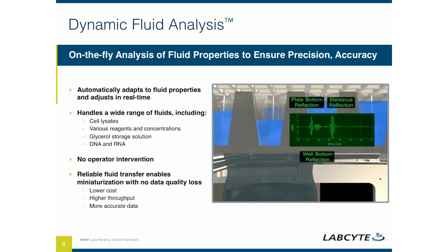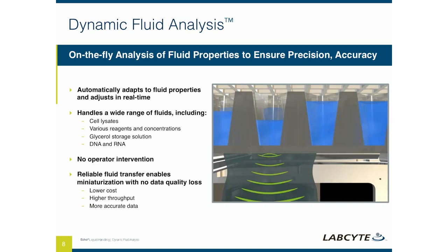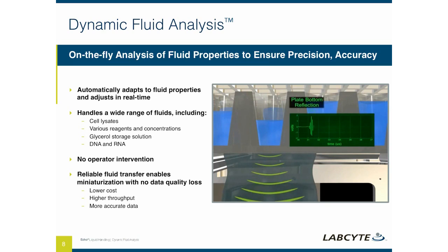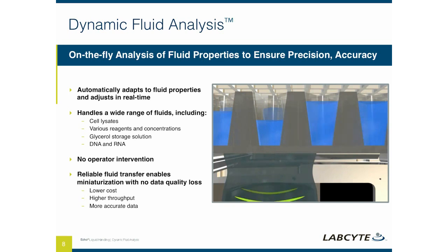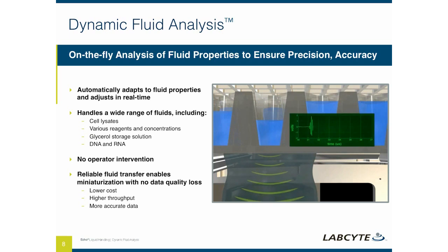So what you're looking at in this video is a situation where the transducer is emitting a low energy pulse into the well. We get reflections from the bottom of the plate, we get reflection from the bottom of the well, and we get a reflection from the top surface of the liquid. So that is the meniscus reflection. And through analyzing the strength of those reflections as well as the time differences between those reflections, we can start to determine a variety of different characteristics of the fluid that's contained within that well, including the surface level.